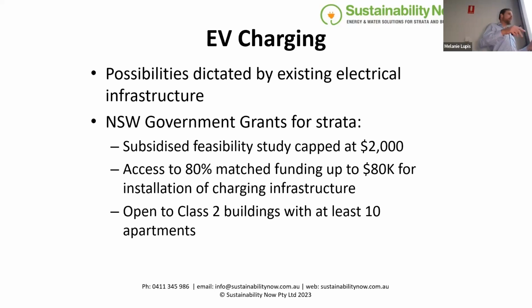The first limiting factor is whether you have enough space on your electrical distribution board or main switchboard chassis, and whether there's actually a spot for a circuit breaker that can handle the EV chargers. That's the first roadblock. Then it's a question of how much that main switchboard can handle where the electricity comes in from the grid, and then the next problem is whether the substation supplying your building can handle that extra load. That's where it gets really hard.